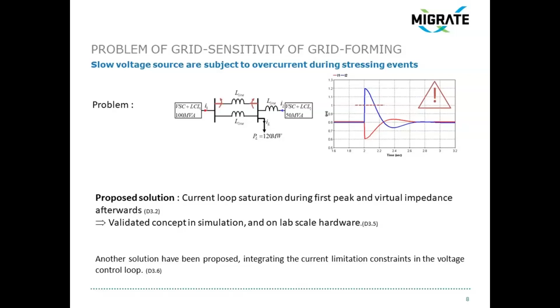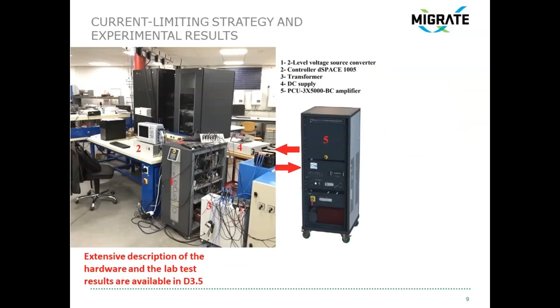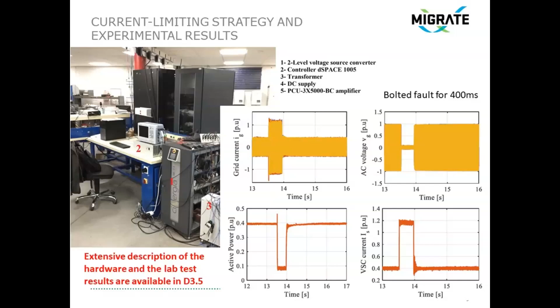So we had this, with a 7 kVA inverter where we can plug all the controls that were developed in MATLAB, and we have a transformer, and then we can plug it directly to the distribution grid or to an amplifier. More tests. So here is a result of a voltage fault for 400 milliseconds, and we see that the current is just hitting the 1.2 per unit. That was the limit of the inverter that was also set in the controls. So even with some measurement noise and a real installation, we managed to have very nice current limiting that fitted the 3 controls that were developed, which means that it could probably be plugged to any kind of grid forming controller.